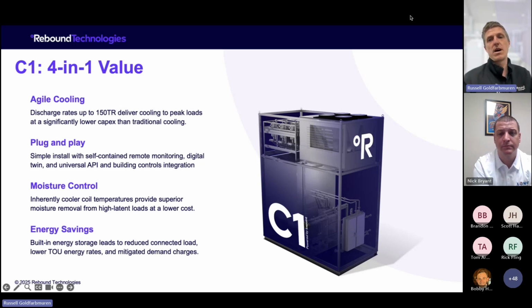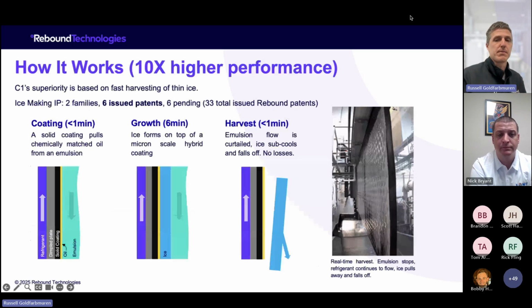A couple other values in our system: everything is plug and play. So, it's just a box. It sits outside. You connect power and coolant lines and you're done. There's no system engineering around what chiller should go with what ice tank, should go with what valves. All of that is built into the system. We're really good in high latent load facilities because our coil temperatures are low and our sensible heat ratio is really good. We tend to excel at those kind of loads. And then also we deliver all the energy savings of a traditional ice storage system with the added benefit of the agile cooling leads to a lot of really great impacts on connected load and interconnection. And I'll hit on that in a little bit.